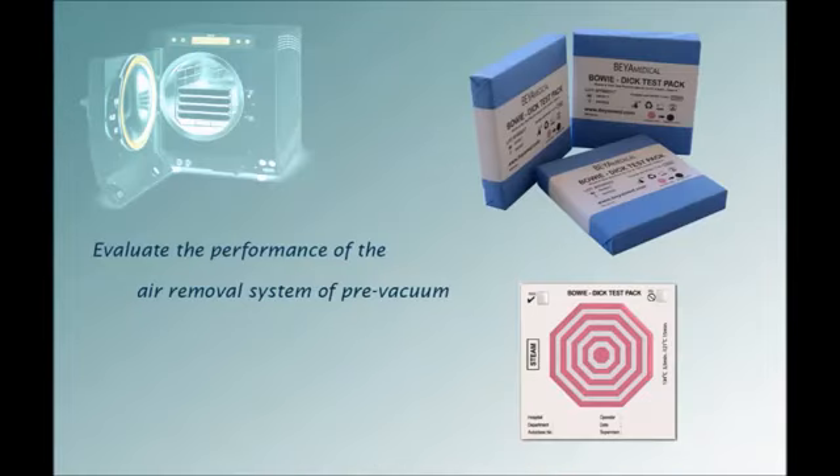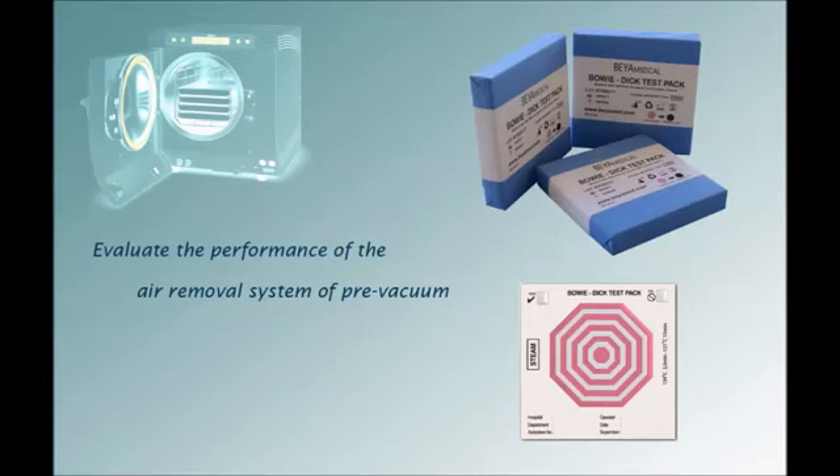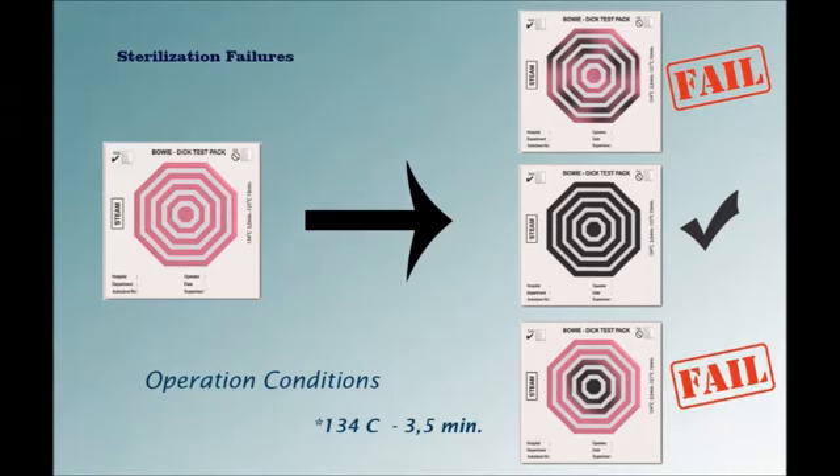BEYAmedical Bowie-Dick test packs are pre-assembled, single-use test packs designed to evaluate the performance of the air removal system of pre-vacuum-equipped sterilizers manufactured according to EN285. Several versions of these test packs are available. A uniform change from pink to dark black on the indicator sheet indicates that all the air was removed and replaced by steam. The back side or front side of the indicator sheet contains all important traceability details, which can be filled out and kept as a permanent record.